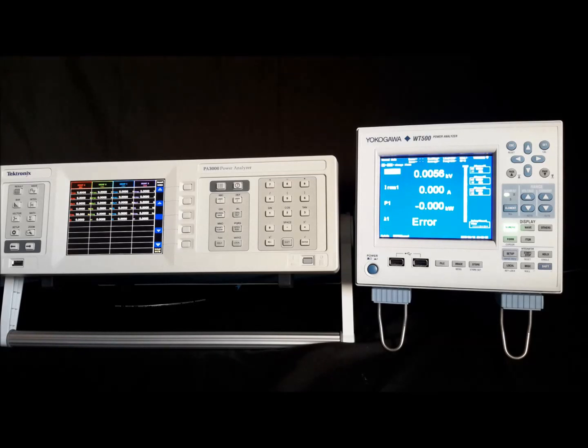For this comparison, as part of the tests I'm going to be doing, I'm going to be using a function generator. The channels have each got a BNC two-way splitter on each. That basically means that any individual channel measurement uncertainty can be eliminated, as the splitter goes into the corresponding voltage and current inputs on both units. The current measurement though is done as a voltage input into the external current sensor inputs on both units.